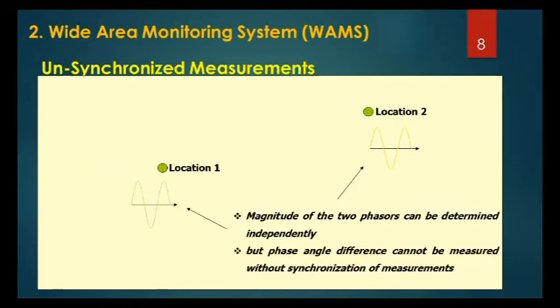Till now, even now, many utilities utilize unsynchronized measurements. Here you can see location 1 and location 2. Now the magnitude of the two phasors, say this is the voltage phasor here and another voltage phasor there, we want to measure the magnitude of these phasors. It is possible to obtain the magnitude of the two phasors and do the measurements in an unsynchronized manner, independently. But if our focus is to measure the phase angle difference, it cannot be done without synchronization of these measurements.